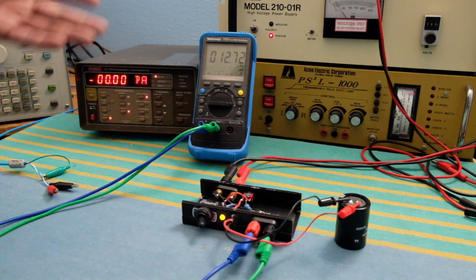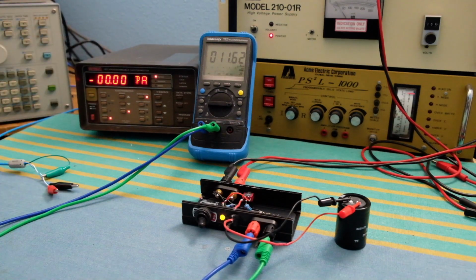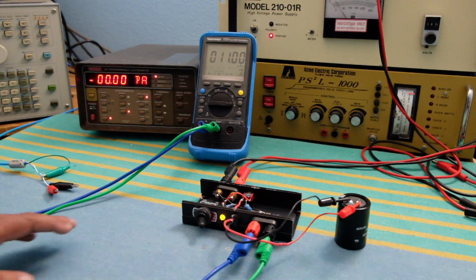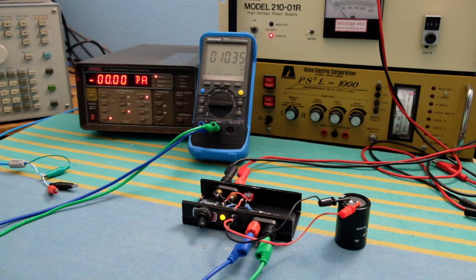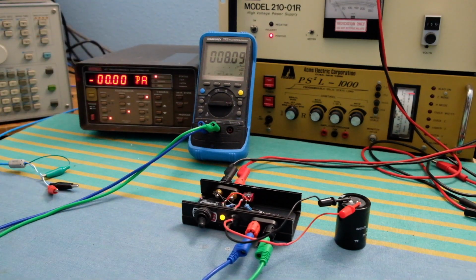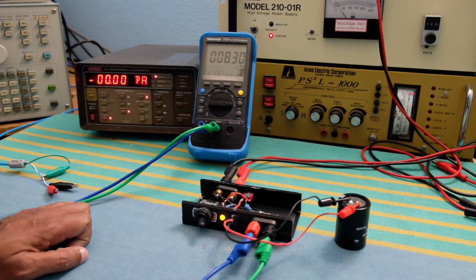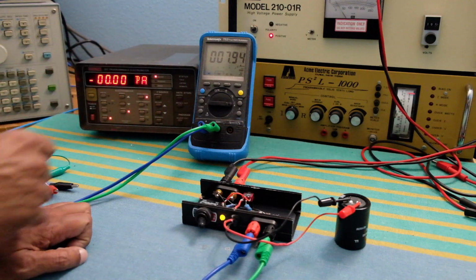So it's been a little over a minute, and you can see it's still falling slightly, but it's I think in the order of 10 microamps, 11 microamps, and voltage is 100 volts. So we'll do some calculations later to see if that makes sense for these type of caps. And typical leakages for electrolytics is based on some general empirical formula of multiplying the capacity or microfarads times the voltage capability and some fudge factors in there, so that depends on the manufacturer as well. So we'll look into that a little bit later, but for now it's still dropping. It's still a very good leakage for a large size capacitor, high voltage capacitor, electrolytic.